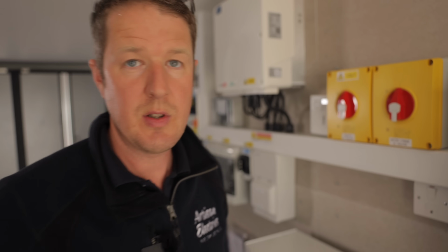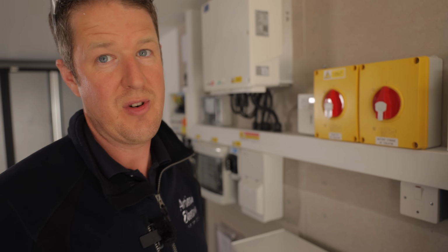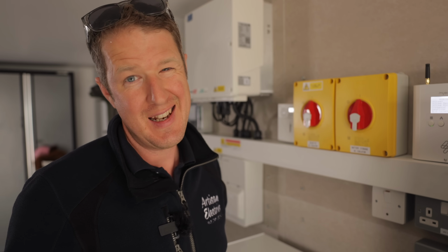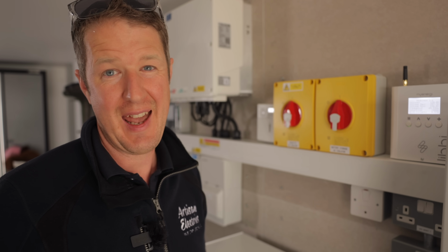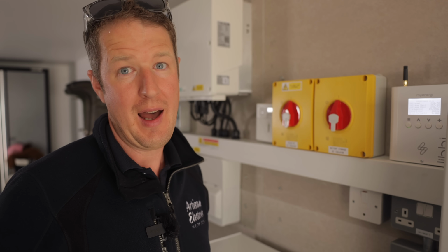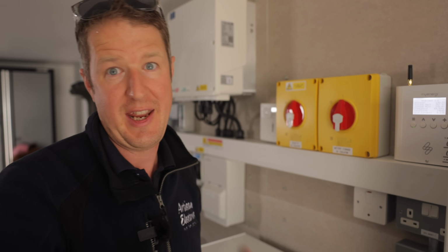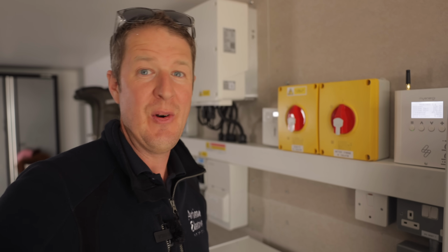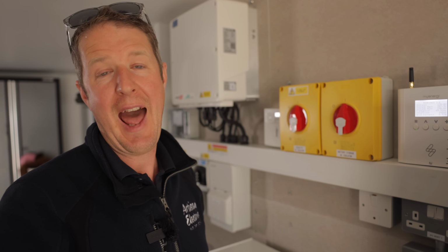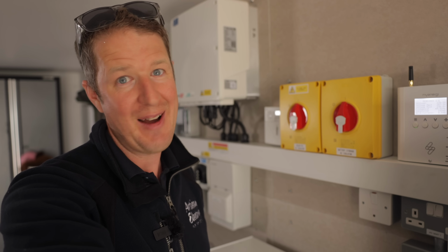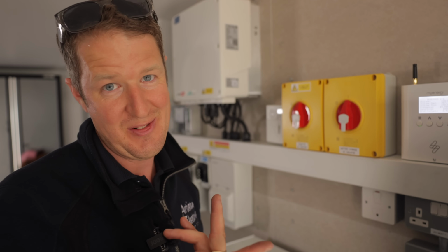Another thing you need to do is check that the grid power CT is reading as expected, whether importing or exporting. An easy tip is to get the customer to turn the kettle on and check you're importing around 3 kilowatts from the grid. If it shows you're exporting power when the kettle's on, then you know the grid CT is the wrong way round.